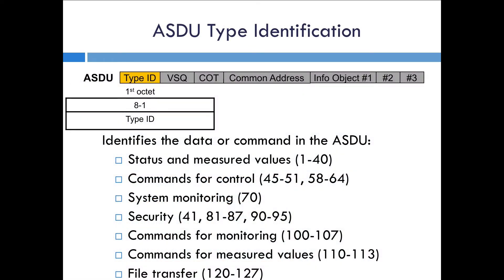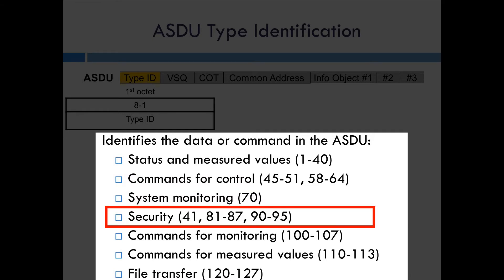The type ID is the first octet in the ASDU. There are up to 127 different ASDU types, grouped into different sections: status and measured values covering the different data types which can be included, commands identifying what type of command request is being sent from the master, and the new security types added for the secure authentication part of the standard. There are also commands for control, commands for monitoring — such as interrogation and reading objects versus commands for setting outputs, binary outputs, and set points — plus commands for measured values and file transfer related commands.